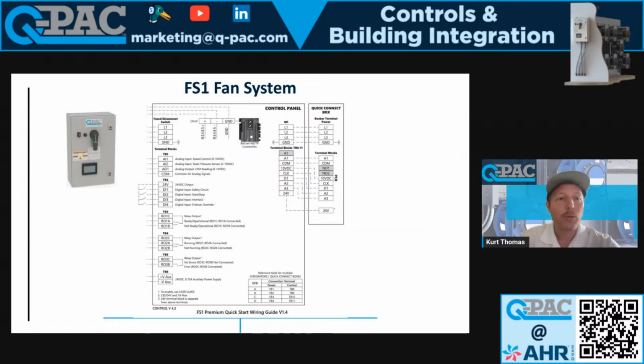All right, so here is a picture of our quick start wiring guide. If you ever have any questions or need a reference for our control side, this is where you would reference. The quick start wiring guide has everything you need to know. The big box, the labeled control panel, is everywhere you connect to all the wires going in and out of that control panel. Anywhere you see a dotted line that crosses that box, that's where you're going to run a line in the field. Not all of them are required.